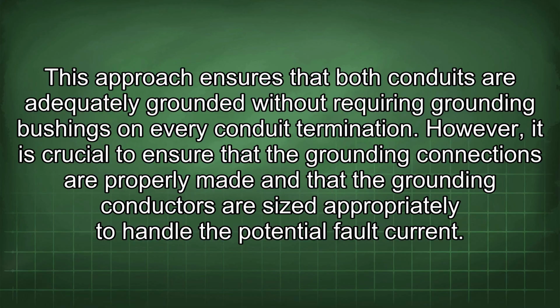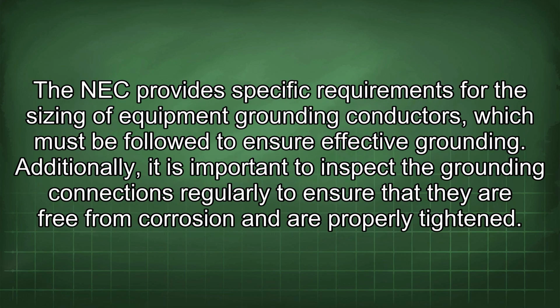However, it is crucial to ensure that the grounding connections are properly made and that the grounding conductors are sized appropriately to handle the potential fault current. The NEC provides specific requirements for the sizing of equipment grounding conductors, which must be followed to ensure effective grounding.